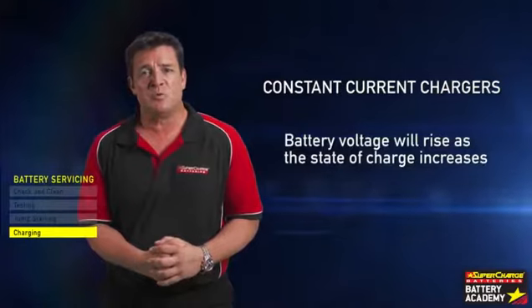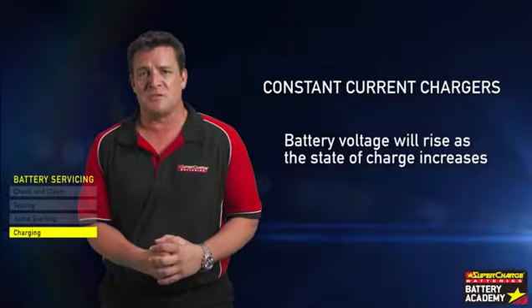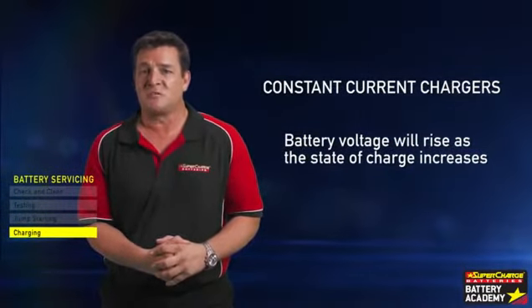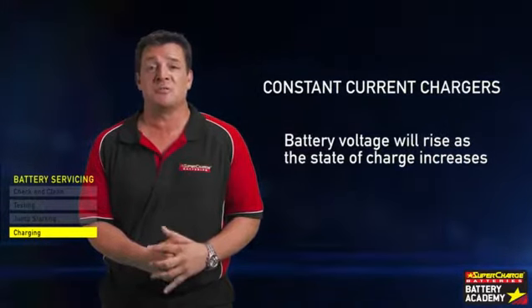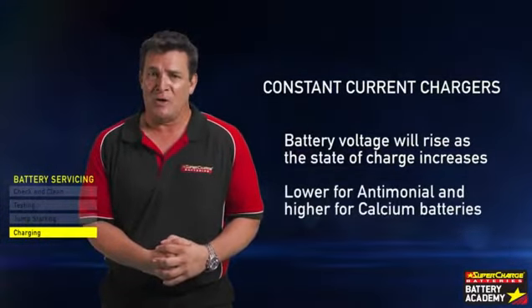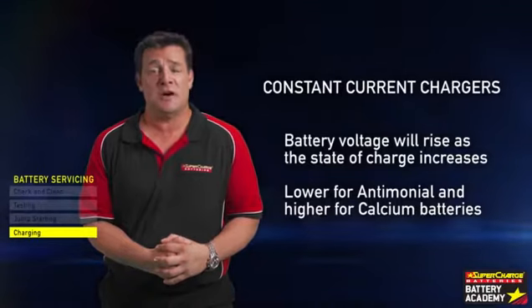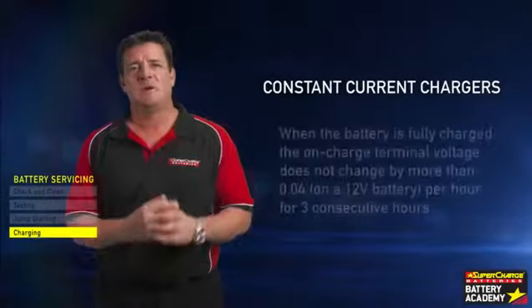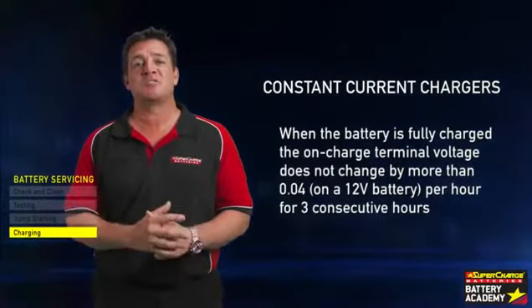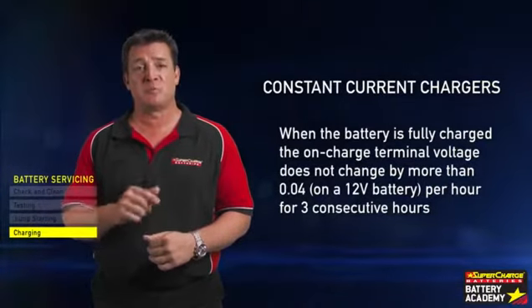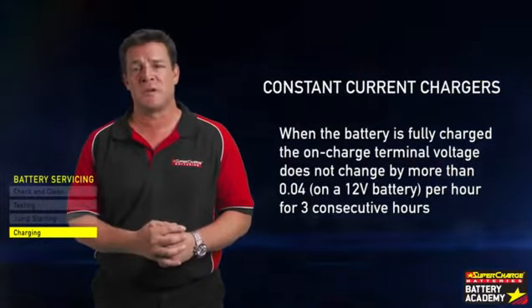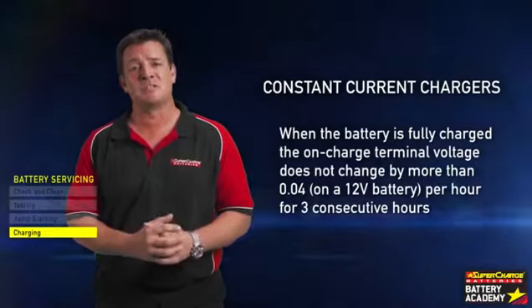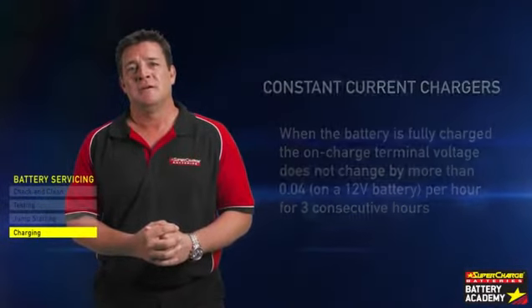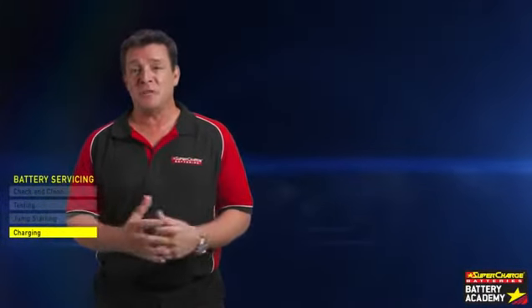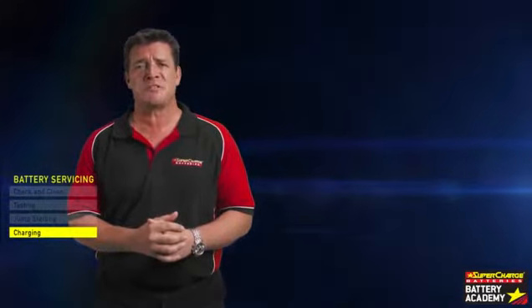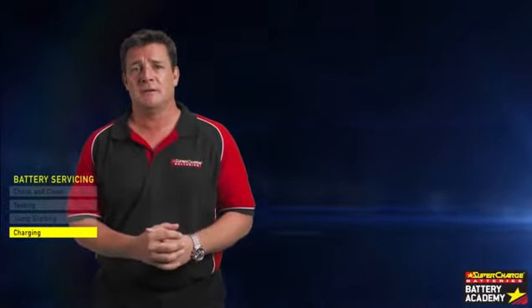The battery voltage will rise as the state of charge increases. The voltage rise of each battery under charge has a natural limit, usually lower for antimonial batteries and higher for calcium batteries. When the battery is fully charged, the on-charge terminal voltage does not change by more than 0.04 volts on a 12-volt battery per hour for 3 consecutive hours. Any charge after the battery is fully charged will result in increased battery temperature and gassing.